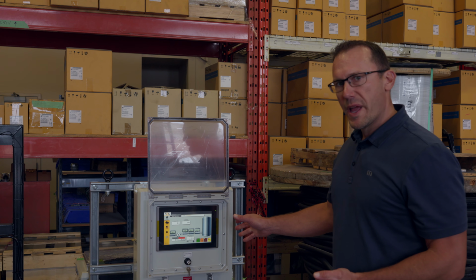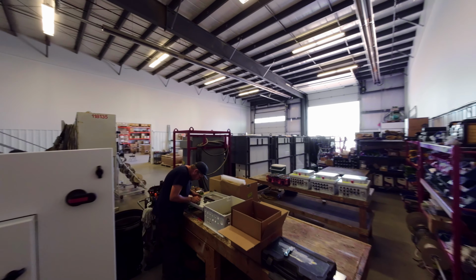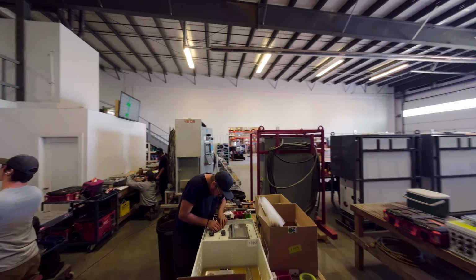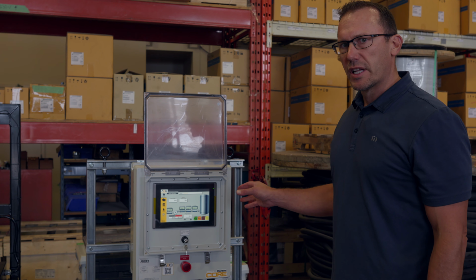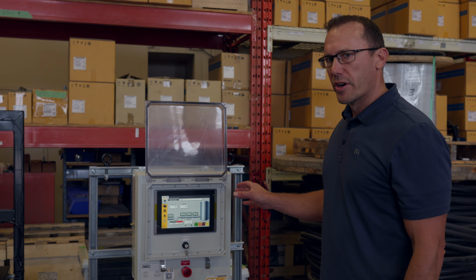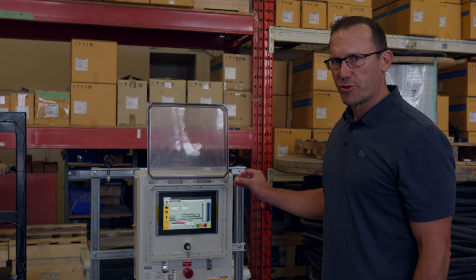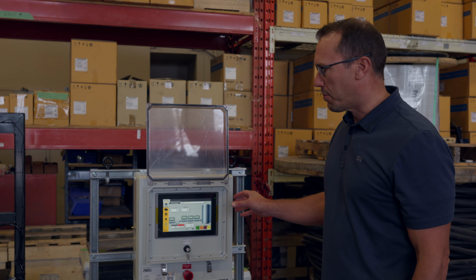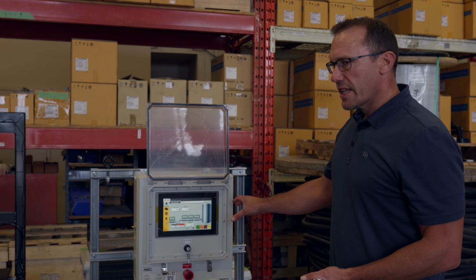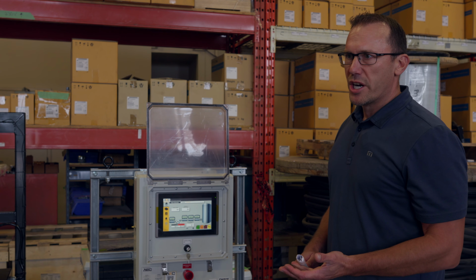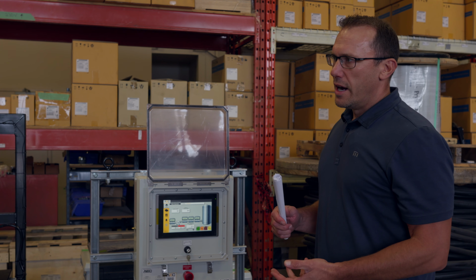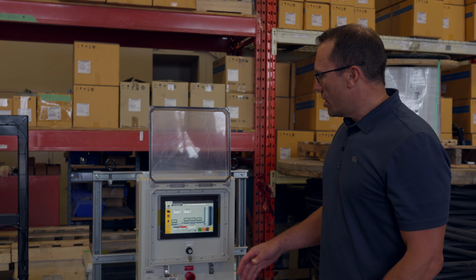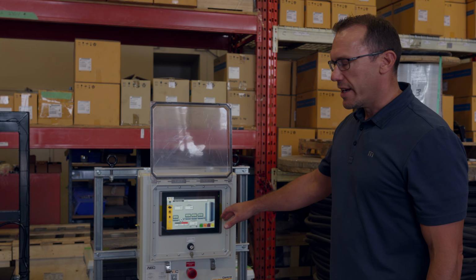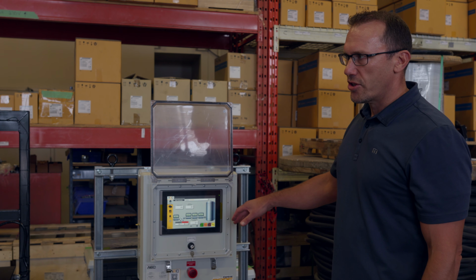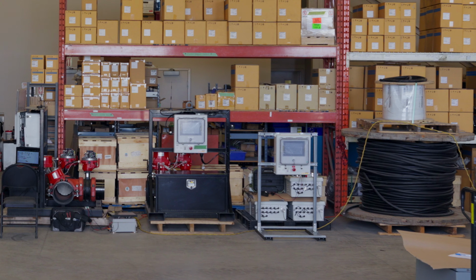Our diesel pump control panel, typically you'd see this mounted on a combustion engine or a diesel engine. But basically we had clients asking us to run their diesel pumps like they run our electric VFD systems for their pumps. Using this, they can run off pressure, flow, inlet pressure, outlet pressure, levels, and it'll have all the shutdowns. They can change their shutdowns, they can change their ramp speeds.